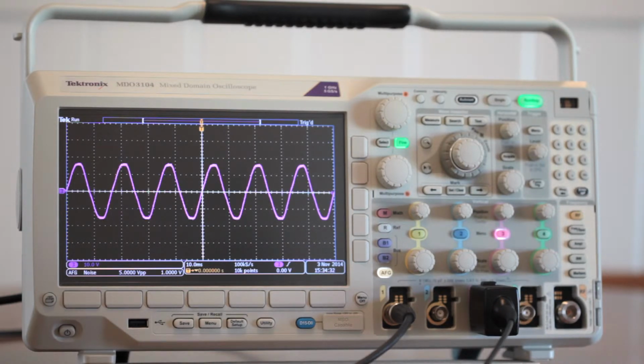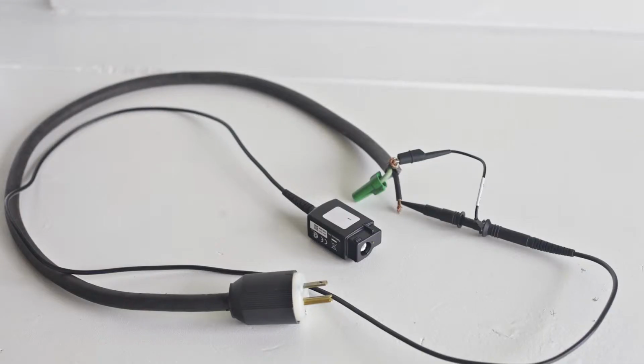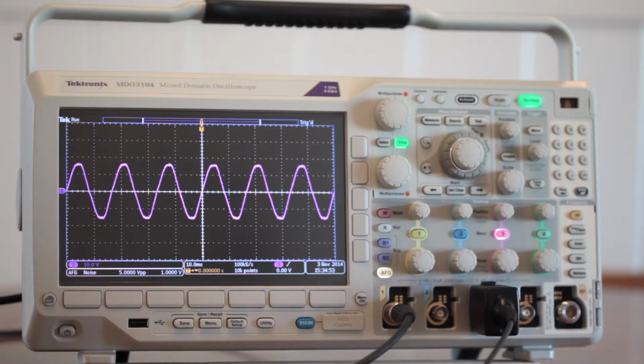First, we've connected the probe to channel 3, analog input. It's connected to the utility AC supply. The probe tip has to be connected to the ungrounded black wire, and the ground reference lead has to be connected to the grounded neutral white wire. And once again, the BNC cable has to be in place.